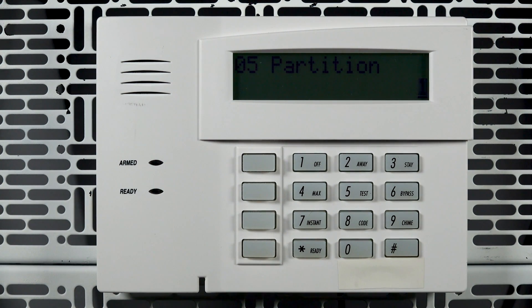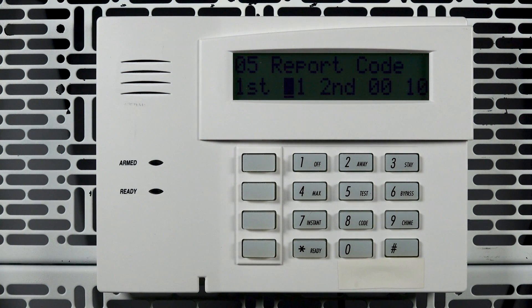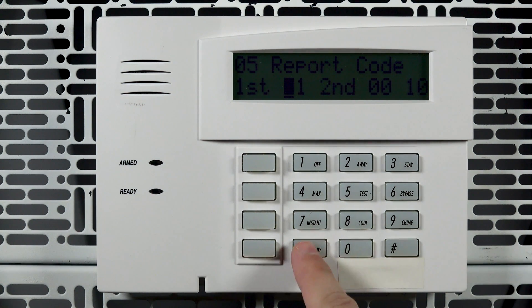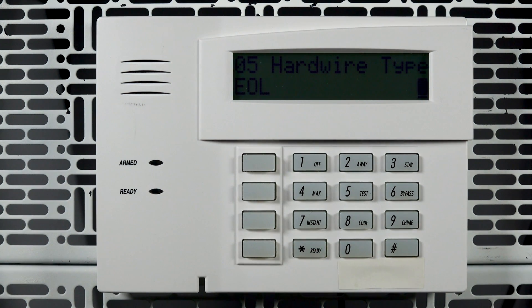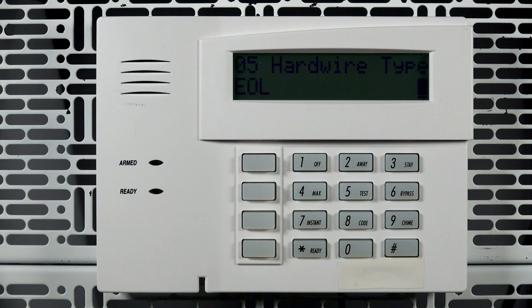Choose the partition for the device, then press Star. For Contact ID reporting, the report code doesn't need to be changed. If you are using another format, please contact your central station for the required values. Press Star. We will leave the default hardwire type as EOL, which is for zones that will be supervised with an end-of-line resistor. A full list of hardwire types can be found in the panel's programming guide. Press Star.